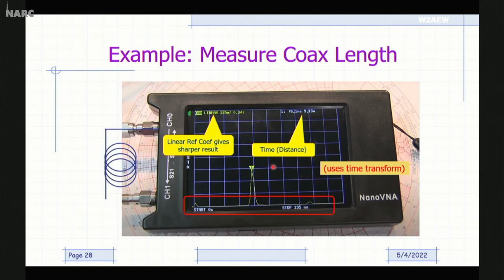And you can actually tell the instrument what the velocity factor is for the coax so that it can, in the marker value, report it back in distance. In this case, it was about a 9.1 meter long piece of coax that I had connected up here. And again, using channel 0 but linear gives me this nice sharp peak here. If I had left that at log mag, this would be a little bit more of a rounded shape. It's easier to pick out that peak when it's a linear measurement.